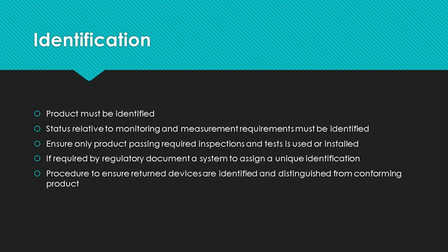Product must be identified throughout the process, including raw materials and components through subassemblies to the finished product. The test status must also be identified — is it tested and passed, failed, or has it not been tested? Product must be identified to ensure only conforming product is used or installed, including components and subassemblies. If required by regulatory agencies, a unique identifier or serial number must be assigned and documented. There must be a procedure to control and identify returned product to distinguish it from conforming product.